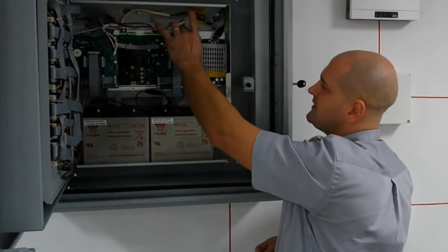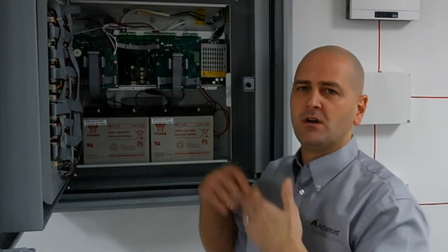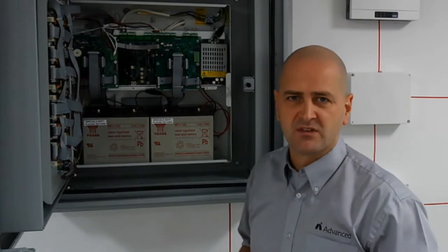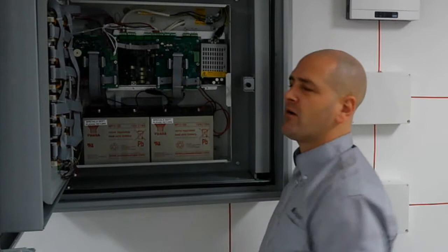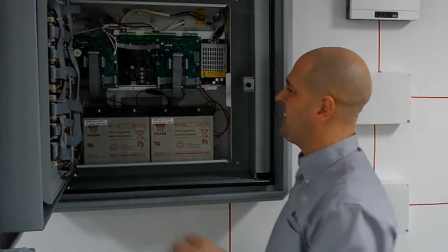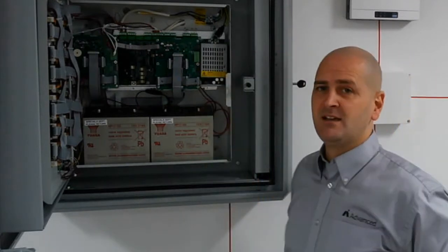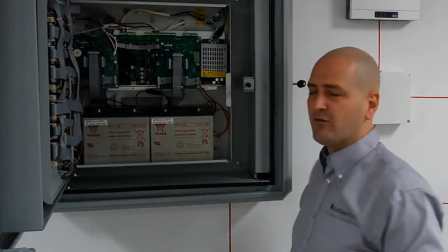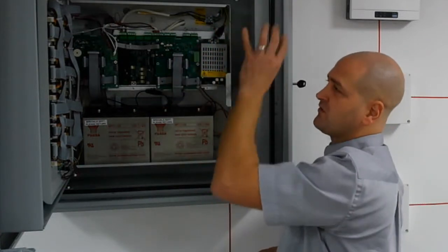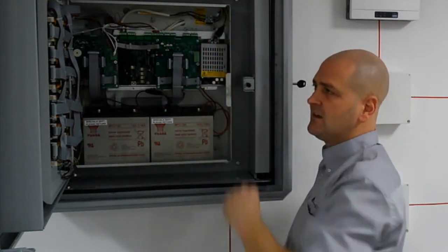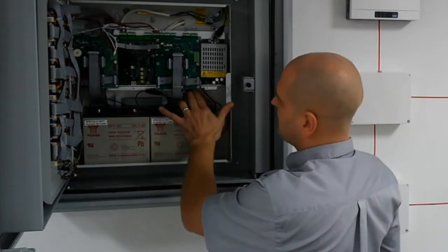Located behind this PCB will be a network card should we need to network it to obtain more loops on the system. Also on here we can mount up to 17 ampere hour batteries within this enclosure. Any batteries greater than this, then we are looking to supply a separately mounted battery enclosure. The remote battery box would then have to be strategically mounted in a secure type location.